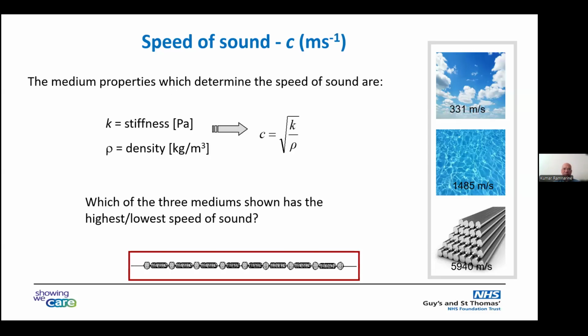And the propagation speed is particularly important for ultrasound imaging because the ultrasound scanner is just listening to the time delay between sending out the pulse and receiving the pulse in order to display the position of the target on a 2D image. So it will have to assume a speed of sound at which that pulse is traveling. And the speed of sound that scanners use is 1540 meters per second. That's an average speed of sound through soft tissue.